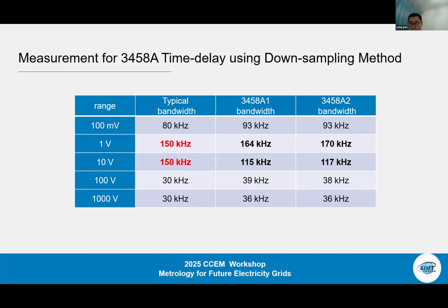2 DMMs are tested simultaneously. The bandwidth of the DMM input pulse is range dependent and also slightly instrument dependent. If the bandwidth is defined as the frequency at which the amplitude frequency response is attenuated to -3 dB, then according to the manual, the input bandwidth of the 1 volt range and 10 volt range are typically both the same, 150 kilohertz, while the test results show that for the 10 volt range, the input bandwidth is lower than 120 kilohertz.